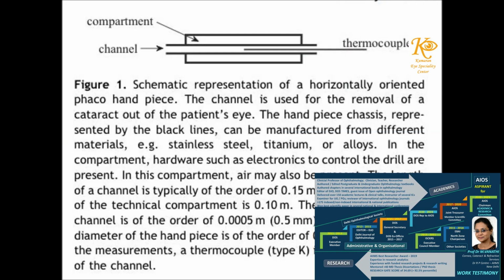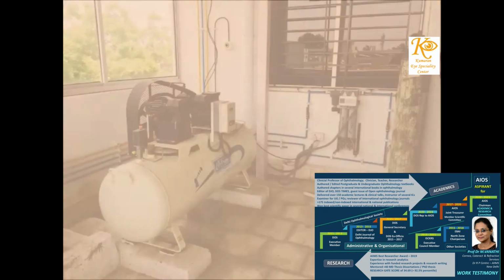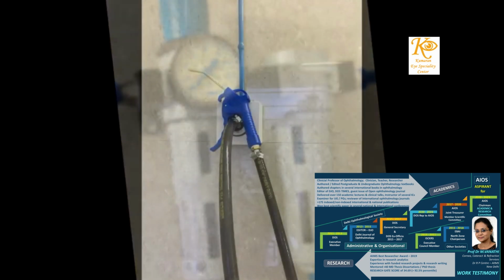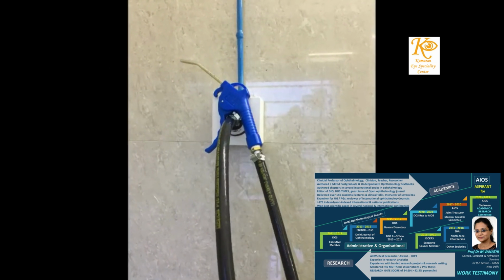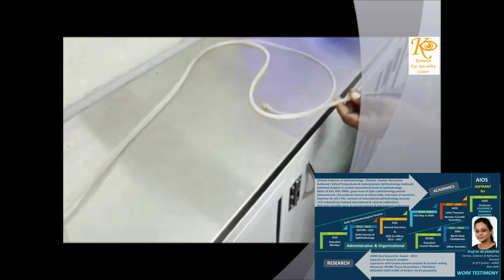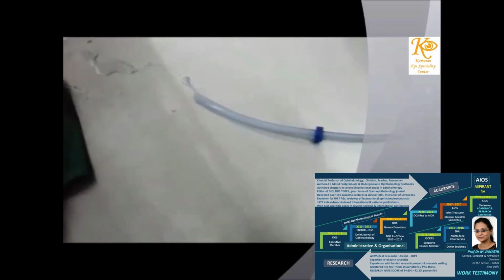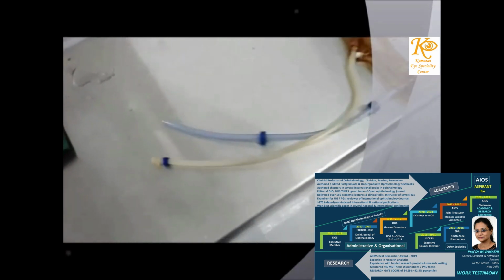This is a schematic diagram showing the internal lumen of the phaco probe, which measures only 0.5 millimeters. Cleaning the phaco tubings to get rid of the moisture is usually difficult and time consuming. The use of filtered and pressurized medical grade air from a compressor, filtered by nanofilters, with a high flow air gun can help to get rid of the moisture in the tubings immediately.